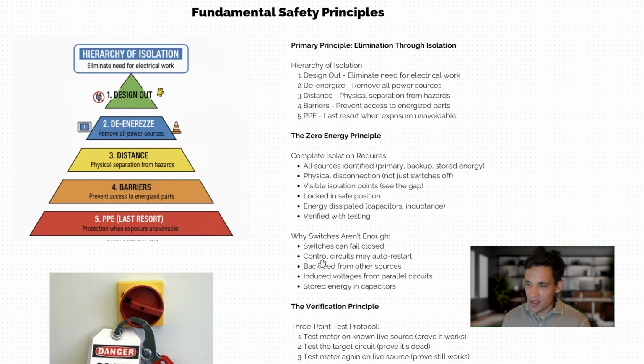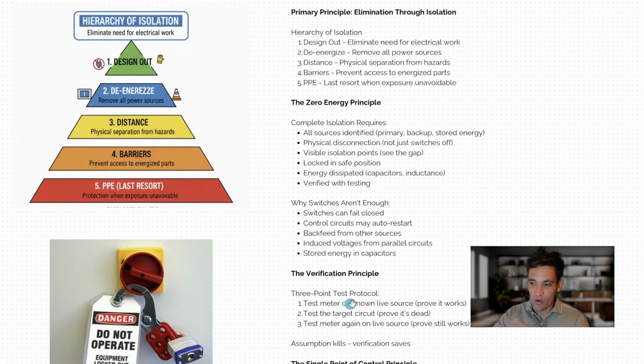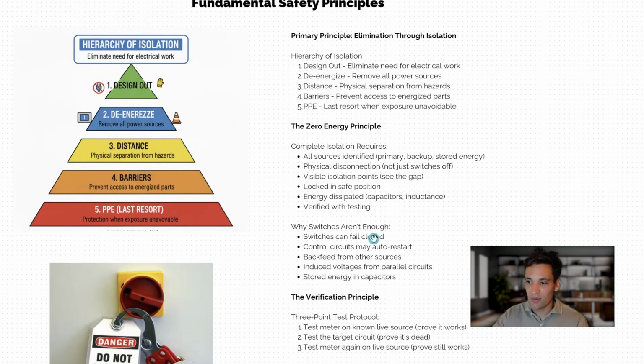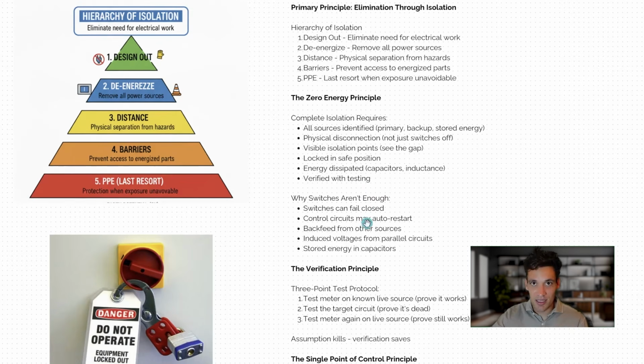Basically, what this all means is that switching the power off just isn't enough. Switches can fail. They can fail in the closed position. Control circuits may auto restart. You can get backfeed from other sources if you haven't properly gone through the drawings and isolated everything. You can get induced voltage from parallel circuits and stored energy in systems. Overall, switching the power off isn't enough. You need a comprehensive way of doing a complete isolation procedure. So at the end of the day, before anyone works on any system, they have to test that it's properly isolated, which comes down to the 3-point test protocol.